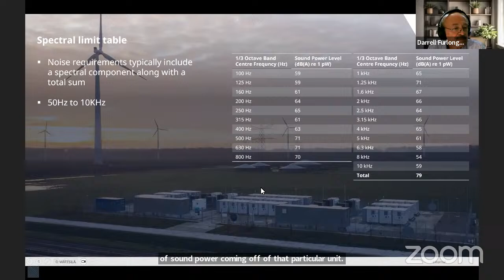At the end of the day, what really matters is what we call far field noise. When you're going into a community, you really want to look at the sound that you're measuring at the property boundaries of that particular energy storage plant. You typically use far field modeling software. CADNA is a very typical piece of software used. We do this at Wärtsilä, and we will do far field noise modeling for a project. We know how much energy is coming off each of our units. We put that into our software, look at the boundaries of the particular project, and come up with what we expect the sound pressure to be at those locations. Based on the ordinance requirements for that site, we then determine if we have to do something with the equipment to reduce the sound power coming off of each of the units.